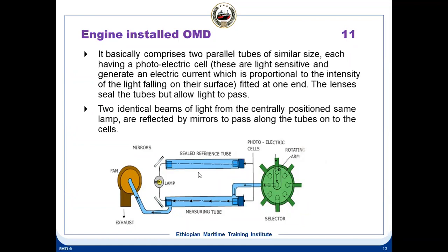And regular maintenance is also to be carried out. Not only this type, the one which has this Visatron and all, they have a lot of filters inside. The filter is a very critical one in the measuring chamber. If the filter gets choked, it gives an alarm. Even if the vacuum pressure drops, it gives an alarm. So these two things are very important. You have to physically come and investigate what is the cause of the alarm.